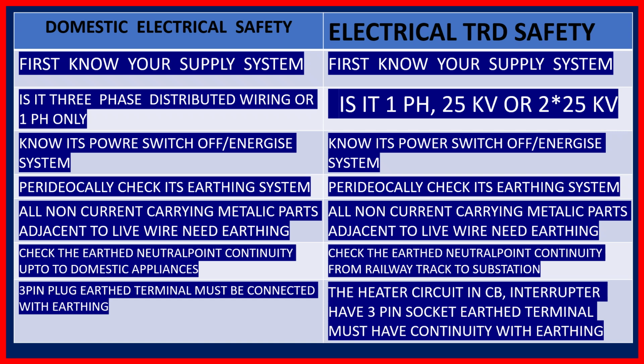So the main thing is earthing, because earth can bear all the charges, and it has only 0% potential and very low resistance. Potential of earth is 0, and with the proper connection with the earth, that means the general mass of the earth, the resistance is reduced very low. In our traction substation, it is kept at 0.5 ohm only. In domestic, 10 ohm is allowed, but in our traction substation, it is 0.5 ohm only.